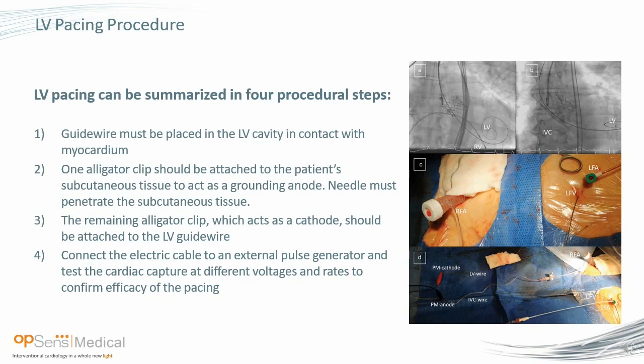I mentioned you want that grounding anode, and you make sure you penetrate the subcutaneous tissue, and then the cathode attached to the guide wire. It's important to make sure that that cathode that's attached to the guide wire is actually attached to the metallic part, not to the coated part. And sometimes it's very difficult to see, so whoever's on the back end needs to make sure that's correct. And then you just test the thresholds.